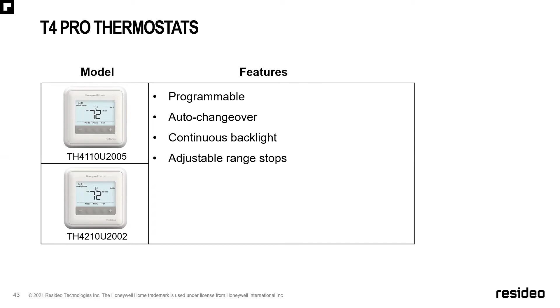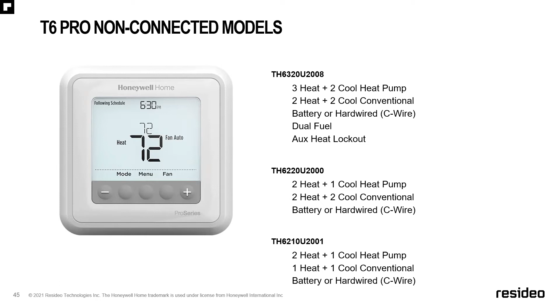Building off of the T4, we've got our T6 Pro. This has a little bit more functionality and more SKUs. Starting from the bottom, our most basic T6 is the 1 heat, 1 cool, or 2 heat, 1 cool heat pump application, the 6210. Then our 6220U is 2 heat, 1 cool conventional, or 2 heat, 1 cool heat pump, and 2 heat, 2 cool conventional. And our 6320 will do up to a 3 heat, 2 cool heat pump.